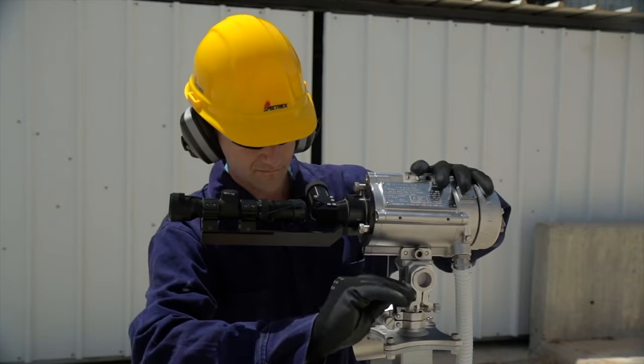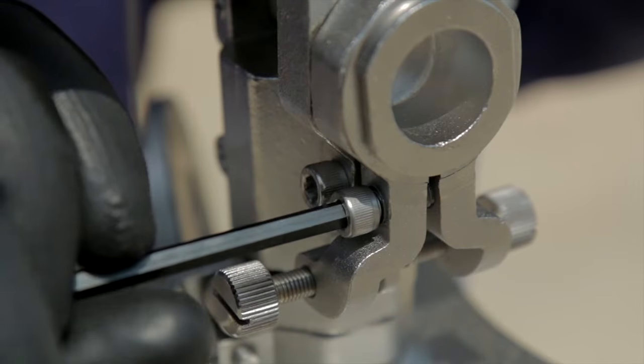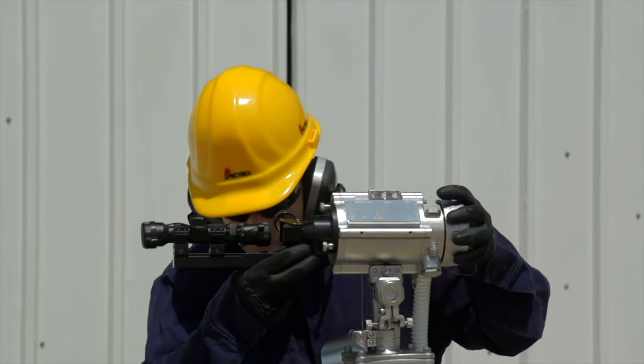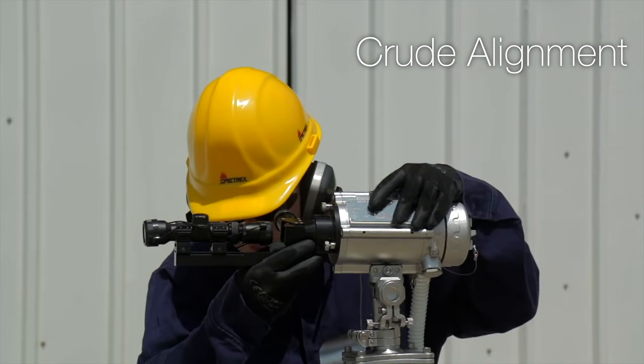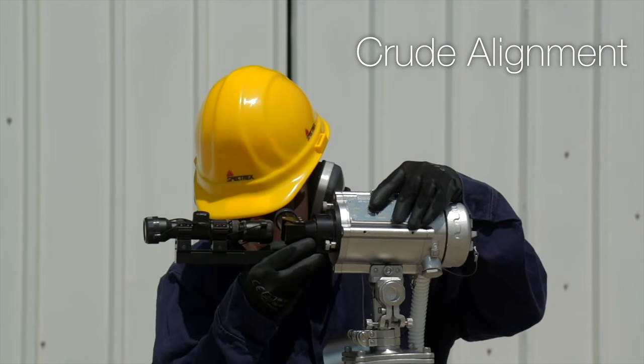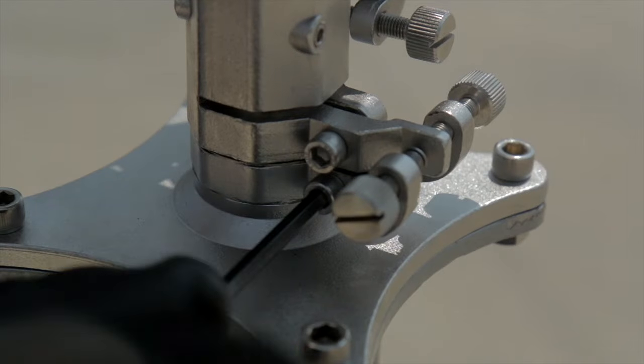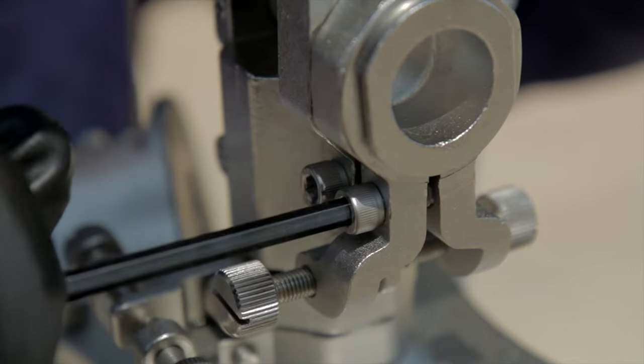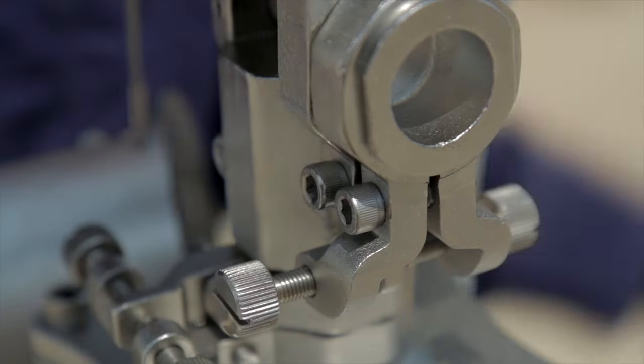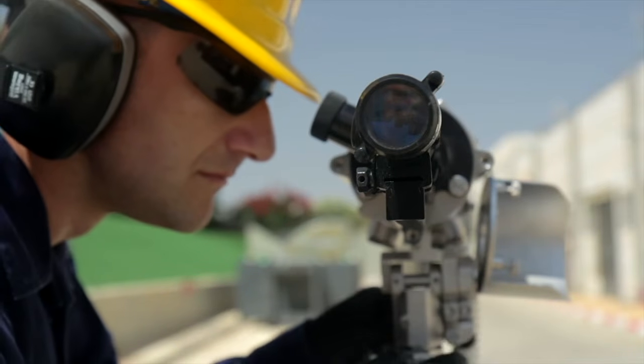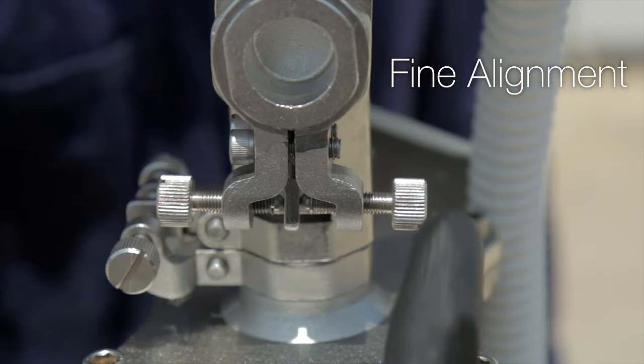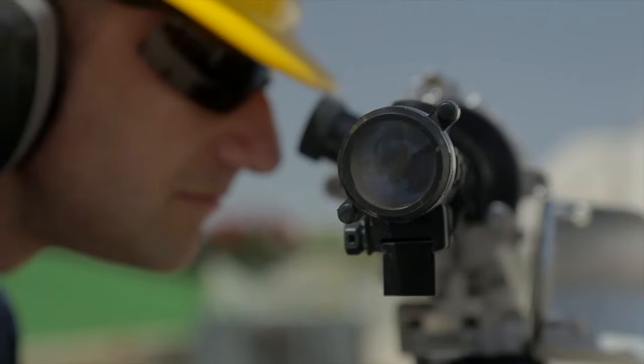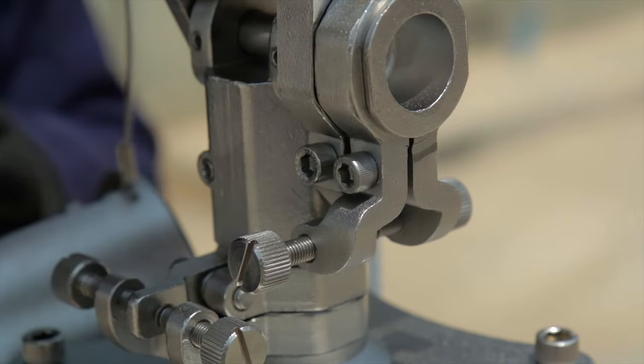Loosen the 2 horizontal alignment screws and the 2 vertical alignment screws to get free range of movement. Then roughly align the source towards the detector. Now tighten the horizontal crude alignment screw and the vertical crude alignment screw. To achieve fine alignment, we'll start with the vertical fine alignment screws. Turn the 2 fine alignment screws simultaneously in opposite directions until bringing the scope to the center of the detector. Then tighten the fine alignment vertical screw.